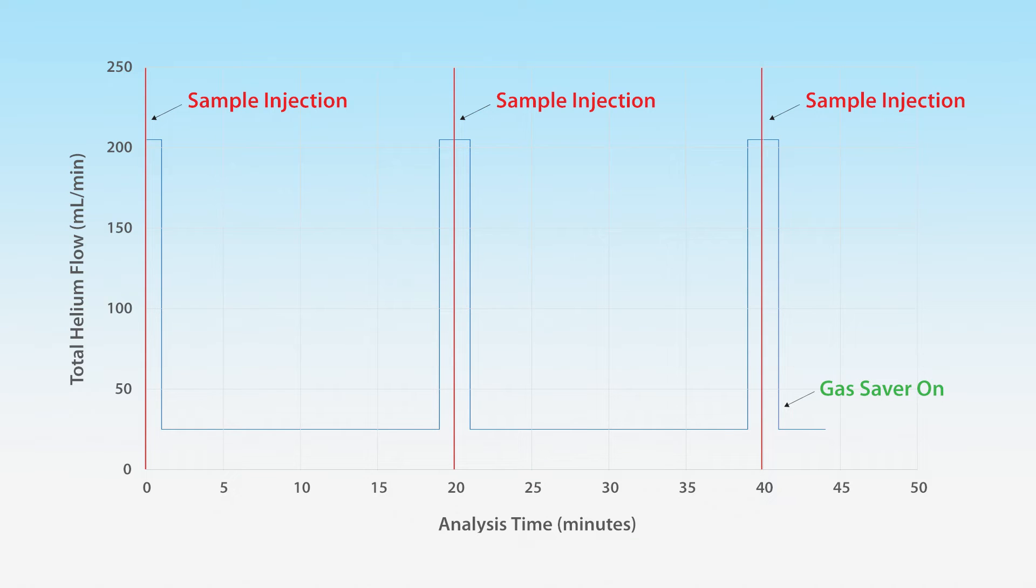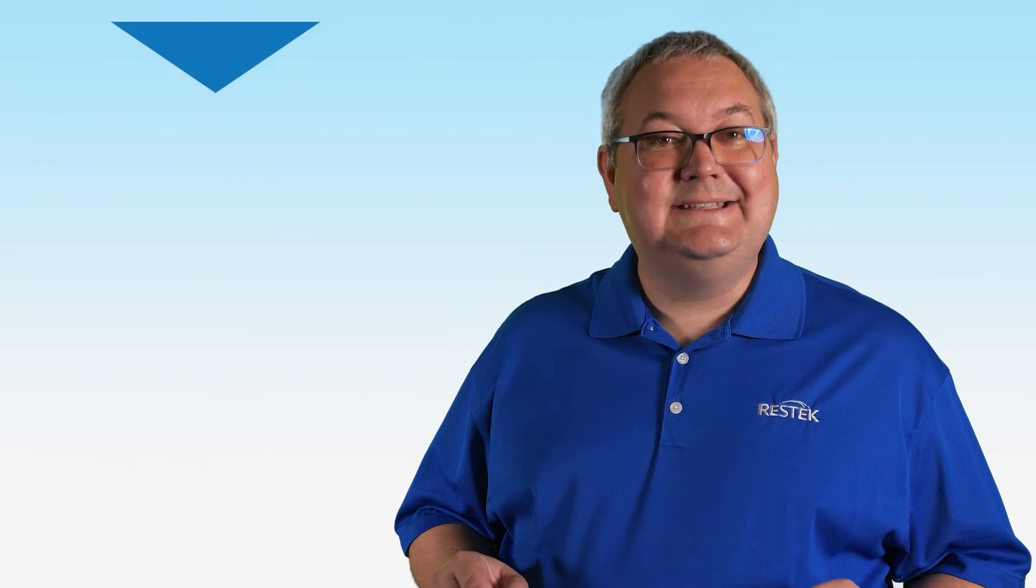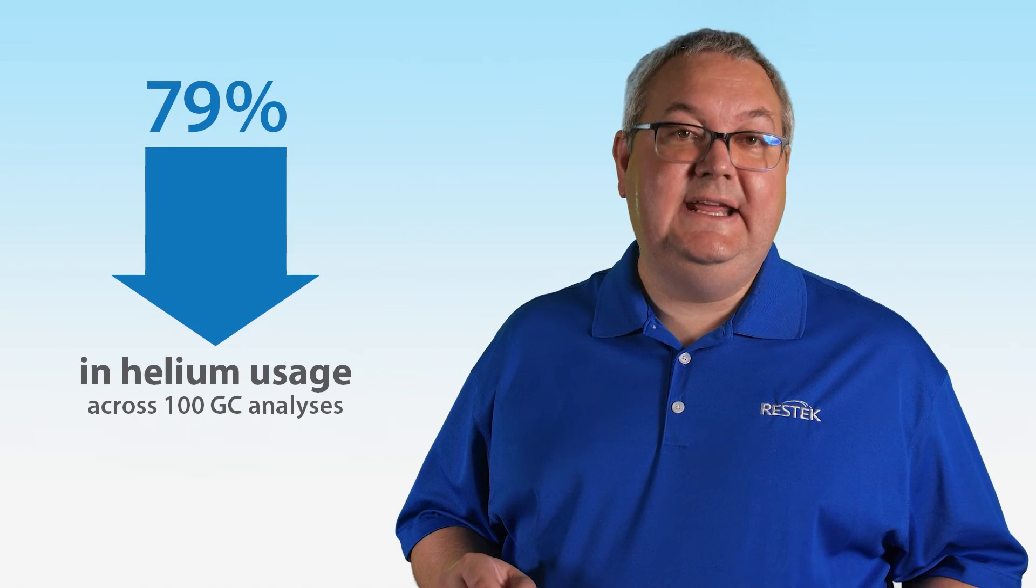Gas Saver Mode will then shut off prior to the next injection. Using our scenario as a guide, you would see a 79% decrease in helium usage across just 100 analyses. Check with your GC manufacturer to see how to use Gas Saver Mode on your instrument.